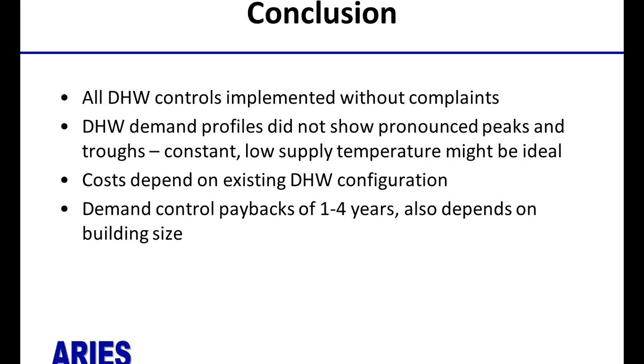To conclude, an important piece, thermal comfort or occupant comfort, all the controls are implemented without complaint. And to be specific, over the 4 buildings over the year monitoring period, we did have 1 complaint to the super that was registered, and he didn't make any adjustments to the controls, and the complaint didn't come back. So we take that as a pretty strong indication of comfort and satisfaction, because people will let you know if they're not getting hot water to take a shower.